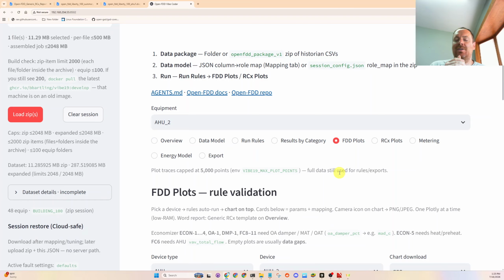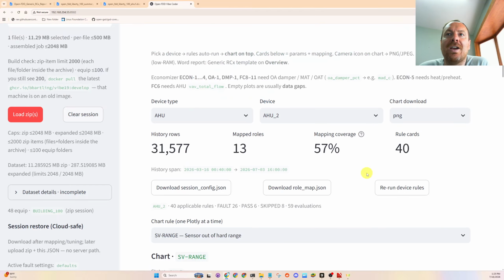Like I said, I'm not going to look very hard at some of those, like sensor range, sensor changes per hour per HVAC type. I don't think I'm going to study those too in depth, just gloss over them once. But the thing that I'm really after is mapping out the heck of running the chiller below 55 degrees Fahrenheit and then economizing. So this economizing fault equation 8, and then some of this duct static stuff. It looks really off to me.